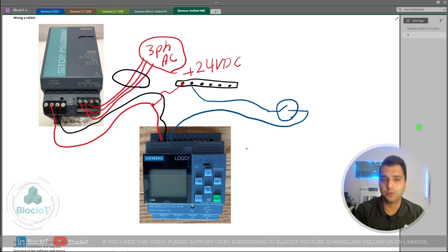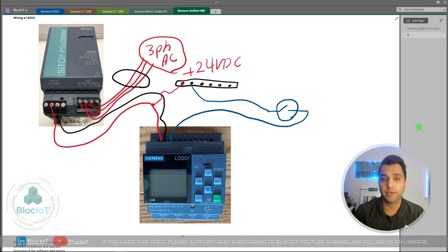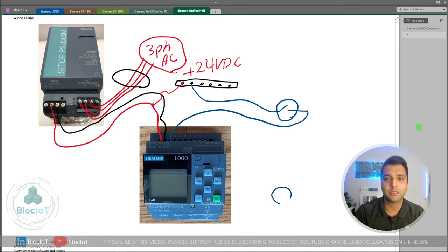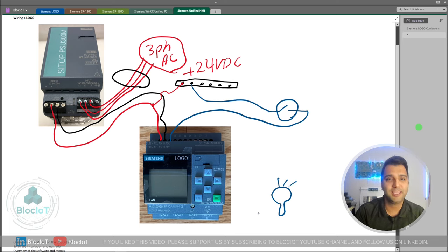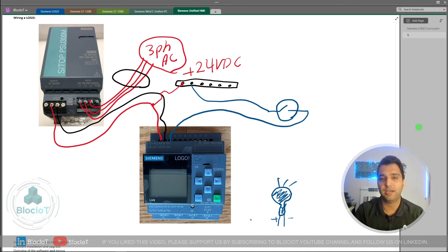There are two main types of digital outputs in Siemens Logo: the first type is a relay output, and the second type is a DC output. A relay output is very simple — you don't need to apply any voltage; it's basically a dry contact. You can directly connect it to a light bulb or a small motor, as long as the motor's amp is under the maximum allowed amp on the Logo.